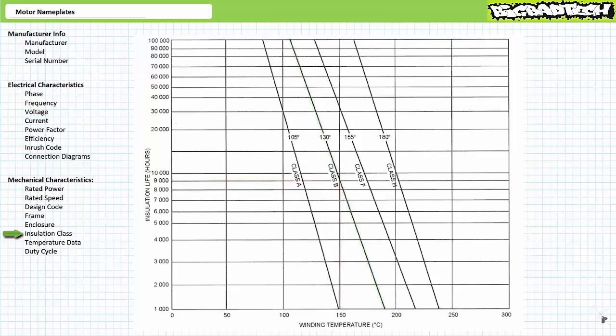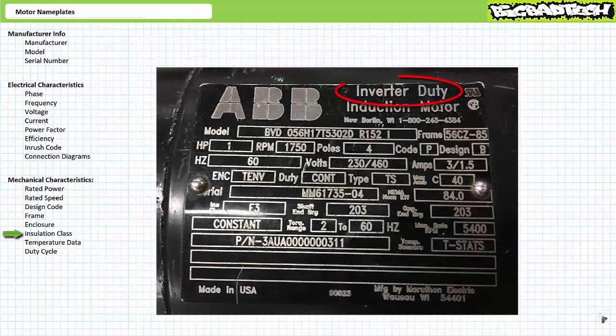We'll examine a special purpose tool called an insulation tester in later lectures that can quantify a motor's insulation integrity. A related entry, inverter or vector duty, if it appears, would designate a motor as being suitable for operation with a motor drive. A motor drive, sometimes called a variable frequency drive, or VFD, or an inverter, is a power electronics device we'll examine in later lectures that can vary the excitation frequency and voltage magnitude to a motor under its direction, and thus change rotational speed and torque. Motors designed to work with motor drives have upgraded insulation and can remain cool even at reduced operational speeds.